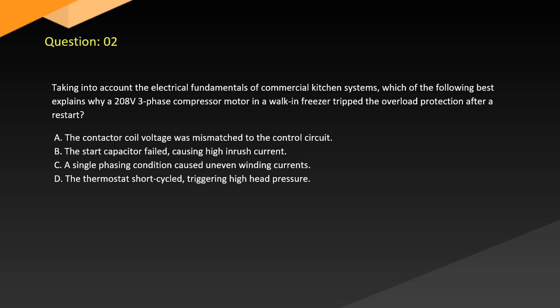Question 2. Taking into account the electrical fundamentals of commercial kitchen systems, which of the following best explains why a 208 V three-phase compressor motor in a walk-in freezer tripped the overload protection after a restart? A. The contactor coil voltage was mismatched to the control circuit. B. The start capacitor failed, causing high inrush current. C. A single-phasing condition caused uneven winding currents. D. The thermostat short cycled, triggering high head pressure.